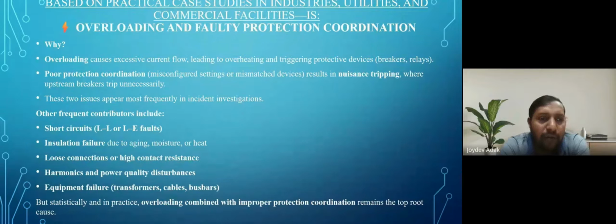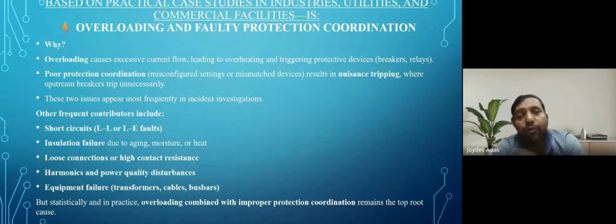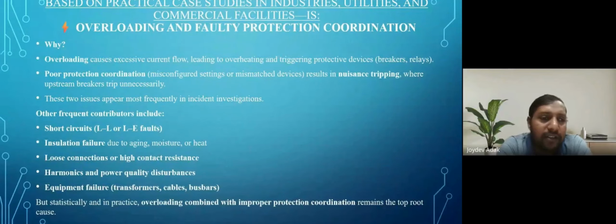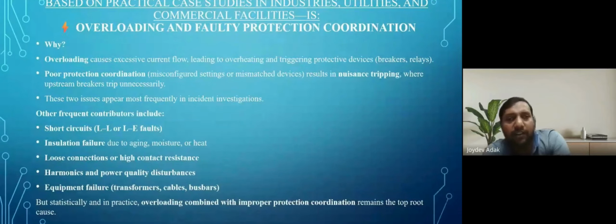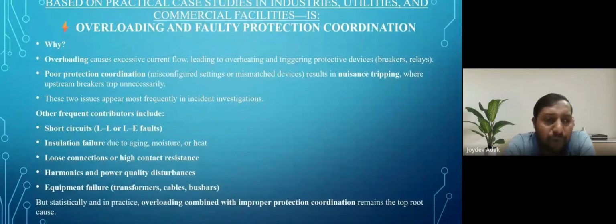Harmonics and power quality disturbances are also present there, and equipment failure may occur. Main equipment failure occurs in 2 types of equipment. The first one is the lightning arrestor. The second one is the current transformer. This is the major failure in any substation or consumer equipment. Motors also fail, but for switchyard equipment there are these 2 types: the current transformer and the lightning arrestor. So overloading combined with improper protection coordination remains the top root cause.